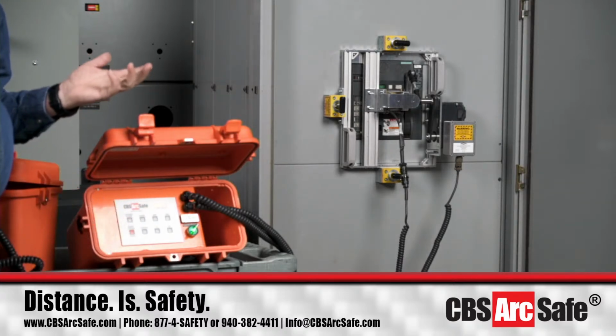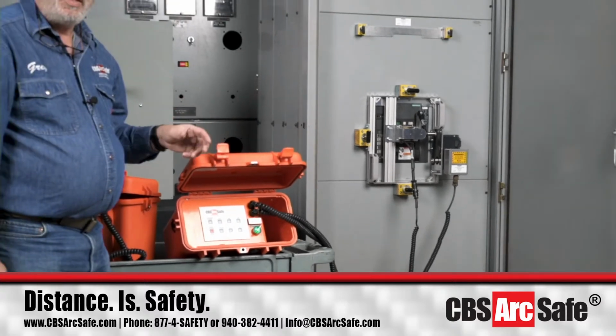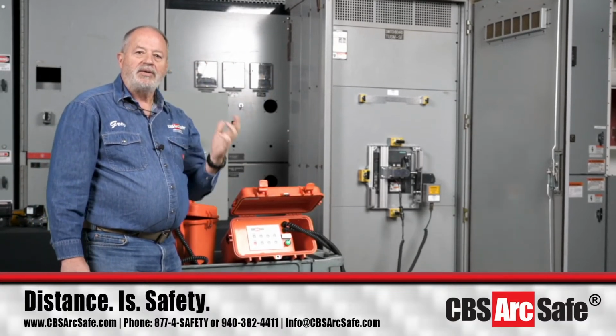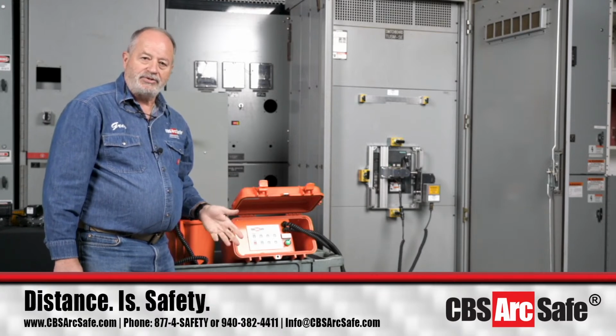Older breakers like an ITE K-line or a first generation GE K breaker, you would move the handle up, pull the handle back down, or pull it down in one stroke, and the breaker closes immediately upon reaching the bottom of the stroke.